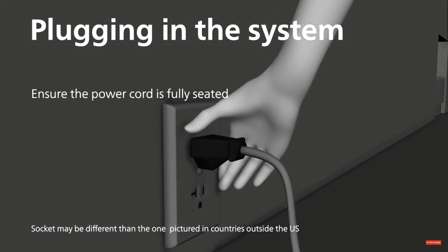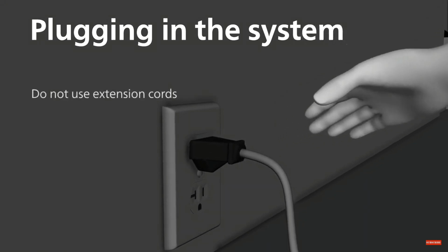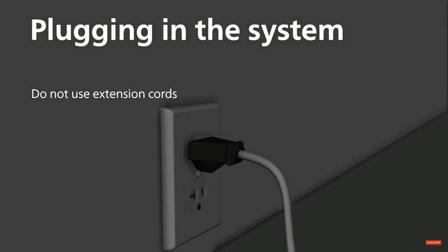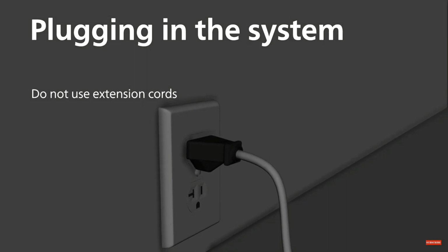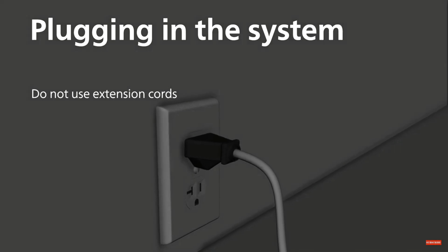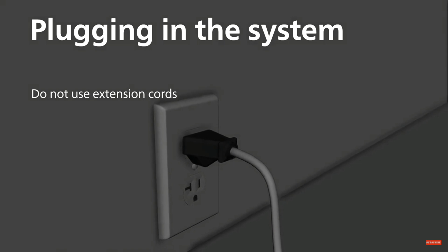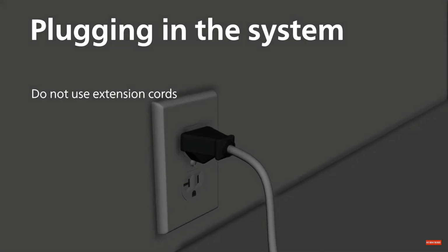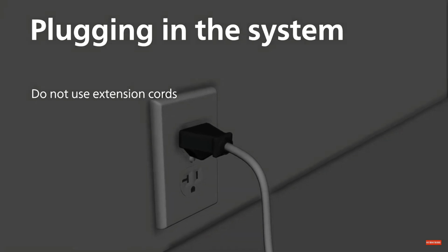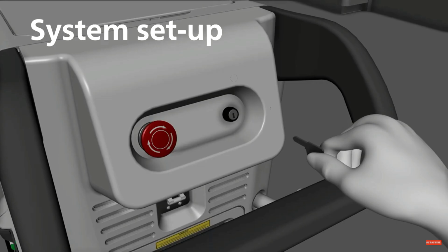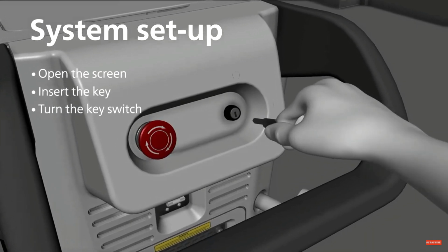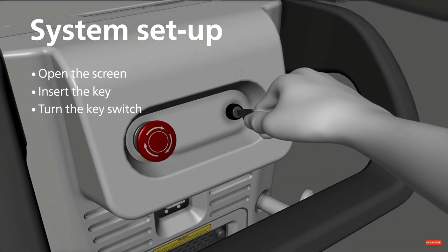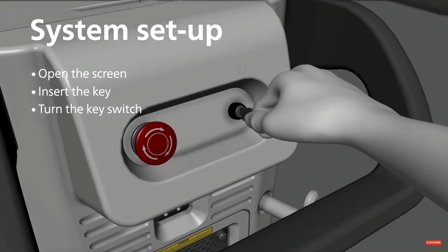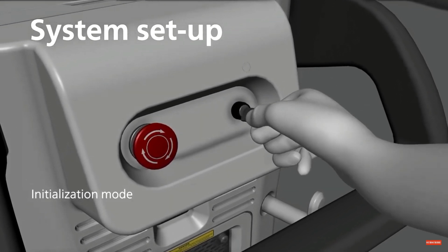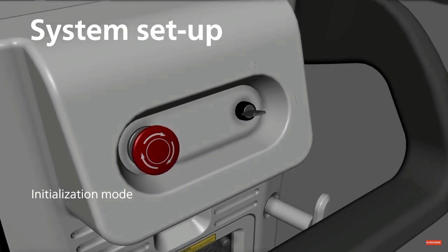Ensure the power cord is fully seated. Do not use extension cords. The 15-foot cord that is included with the system should be usable in multiple sockets in a lab. An extension cord may not supply the expected amount of power to the system. Insert the key into the key switch on the rear panel. Turn the key switch clockwise to activate the system. When the system is activated, it enters initialization mode.